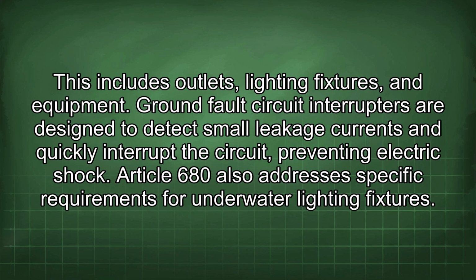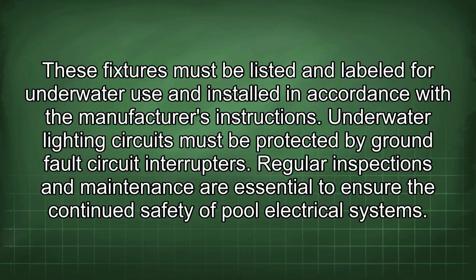Ground fault circuit interrupters are designed to detect small leakage currents and quickly interrupt the circuit, preventing electric shock. Article 680 also addresses specific requirements for underwater lighting fixtures. These fixtures must be listed and labeled for underwater use and installed in accordance with the manufacturer's instructions. Underwater lighting circuits must be protected by ground fault circuit interrupters.